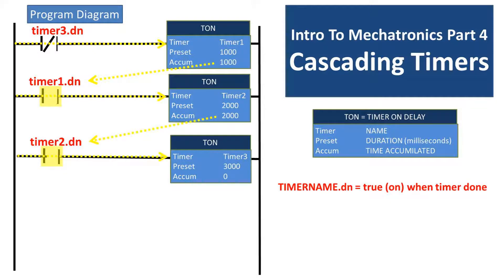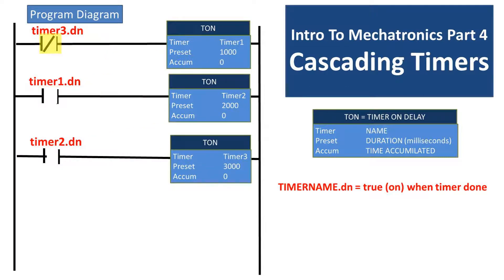Next, timer2 will finish, which will activate the timer2.done normally open contact. This will start timer3, and timer3 will run for 3 seconds. After timer3 is done, it will activate the timer3.done normally closed contact, which will briefly open the circuit when activated and reset timer1. It will then cascade all of the timers and reset them to 0, then become normally closed again and start timer1. Then the process repeats.